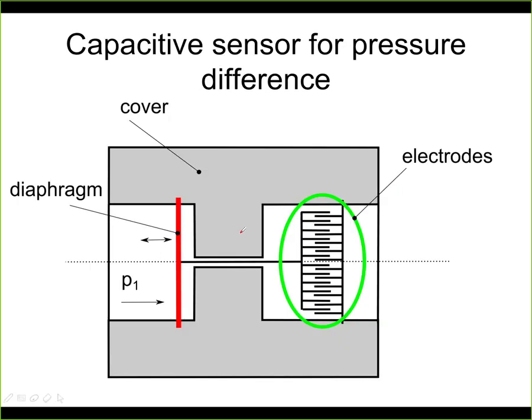Here is another example of exactly the same principle. Here we see that this is a diaphragm. The measured pressure is connected from the left, so there would be an input port. And here on the right we have a set of electrodes. As this diaphragm changes its shape, if we apply more pressure P1, then it gets deformed like this, and it will move this rod, and this will move the electrodes. Now one set of electrodes, the one on the right, is fixed to the frame, and the other one, on the left, is fixed to the rod. So when this rod is moving, we have a change of capacity that we may detect here. So again, we measure the deformation of the diaphragm, but in this case we sense the changes of capacity, not the deformation directly with some strain gauge.